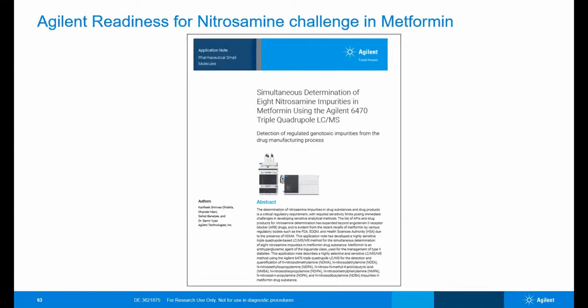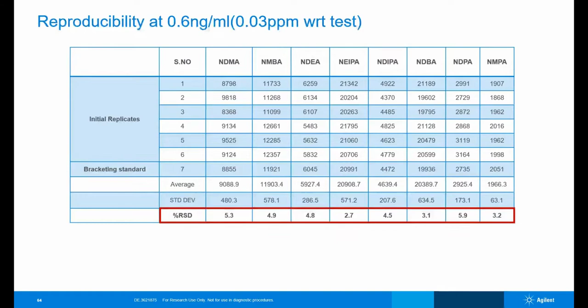Here is the reproducibility data that you can see for 7 replicates, including bracketing standard at specification limit level, which is 0.03 ppm in this case. And you can see all 8 nitrosamines give RSD percentage less than 6% at this low concentration.